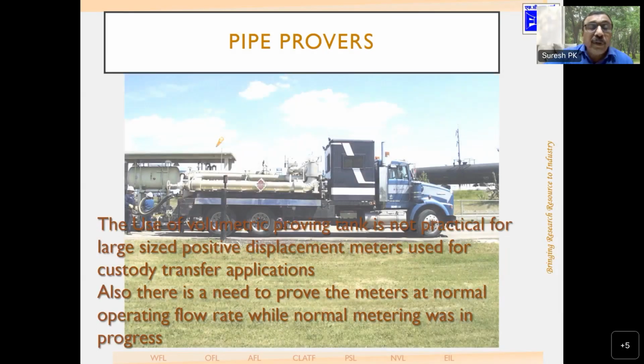Now, there is another method of calibration, which I have mentioned earlier. At FCRI, we don't have pipe provers. Instead of volume tanks, it is not practical to use them for very large flow meters. If you have to collect the volume for 1 minute duration on a large capacity flow meter, you just calculate 10,000 by 60. That much huge volume tank is required, which is not very practical, because if you install such a huge volume tank, then you have to calibrate that volume tank. For calibrating that volume tank, you need another volume tank, which has to be calibrated again. So it's not practical to maintain the traceability, and therefore the accuracy, of the volume tank if you are using very large volume tanks.